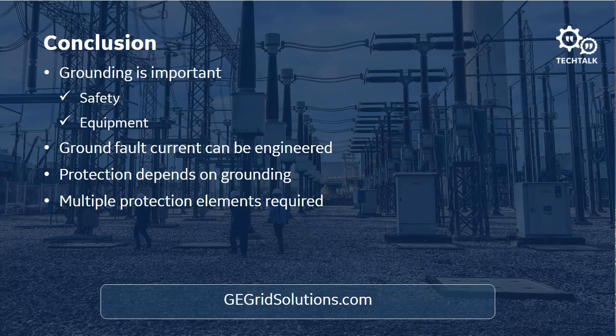I'm trying to read through some of these questions here. For the generator earth fault, if the injection method is not available, then which is the best solution that can be put in? Okay, I'll read it back here. I'm thinking this person is probably from Europe, because in Europe they refer to it as earth fault, not ground fault. So he's asking, if the injection method is not available, which is the best protection that can be used? And I'm making some assumptions here, I'm assuming he's asking about the high impedance protection, where we can use the injection method.